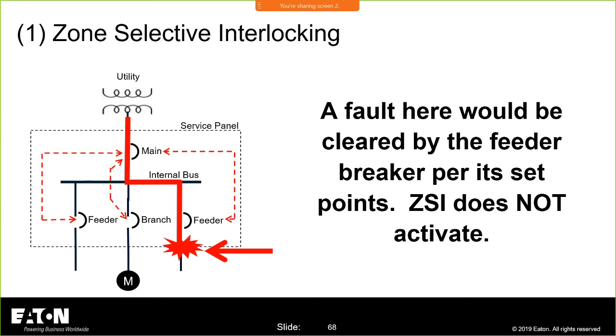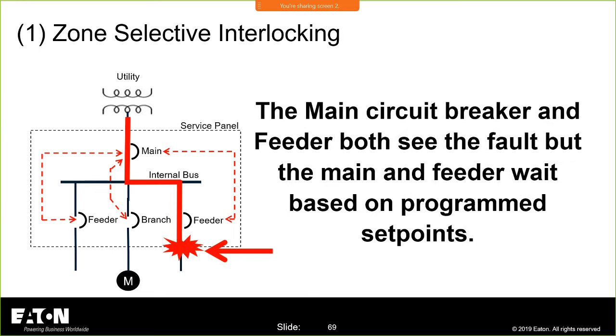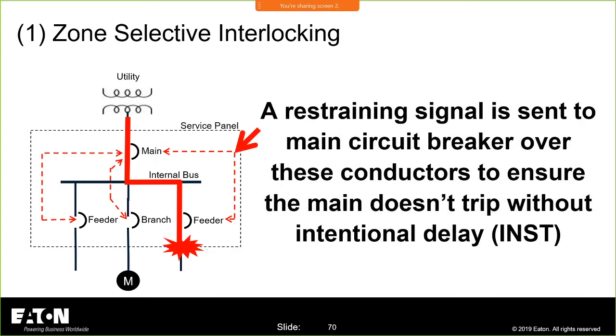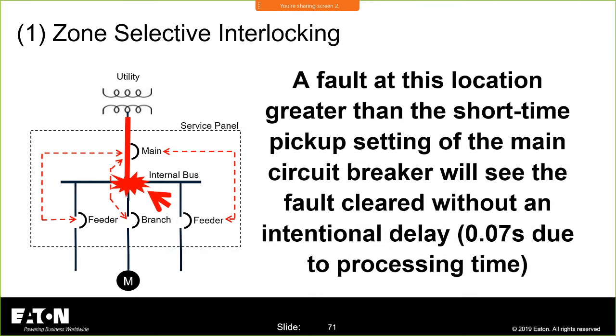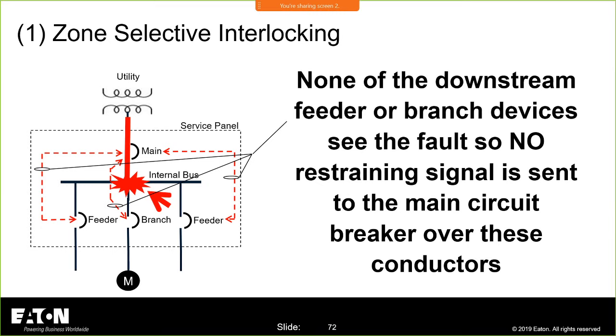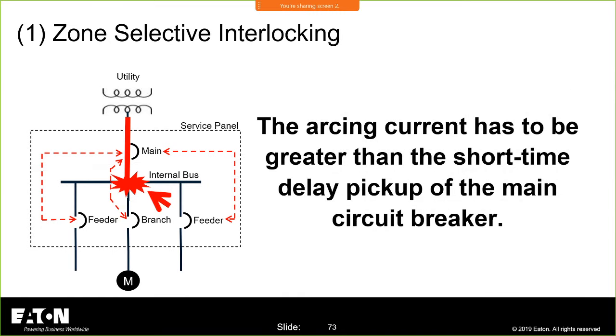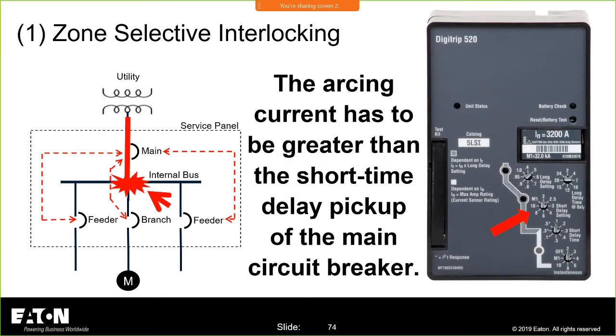Anything that's downstream is outside of the zone of protection. The gazintas equal the gazaltas. That's the way I was taught in school. Those two devices know it, and they all go by their program settings, but if the fault is internal, the upstream device knows the downstream device doesn't see that fault, and it trips without an intentional delay. So on a trip unit, this is your short time delay pickup. That's the setting that's going to be critical for that main device that tells you whether or not it will actuate as an arc reduction technology.